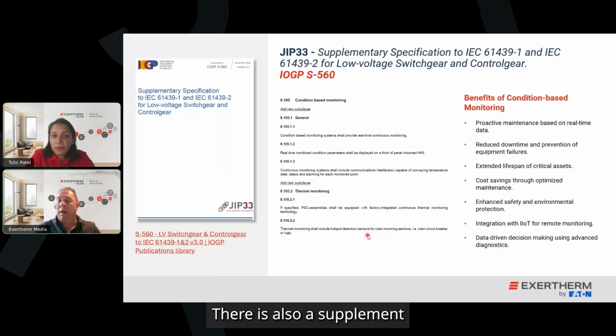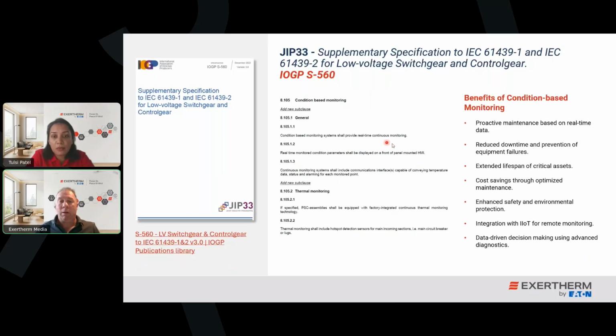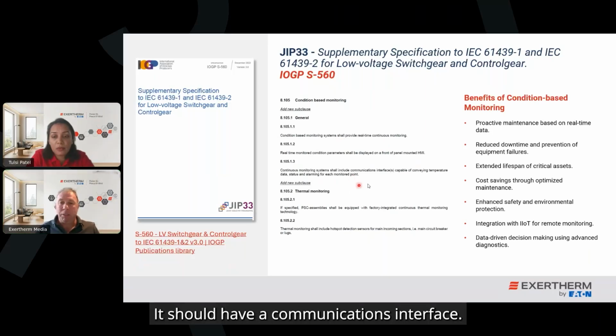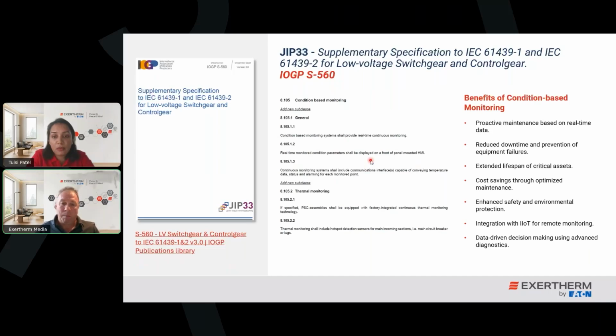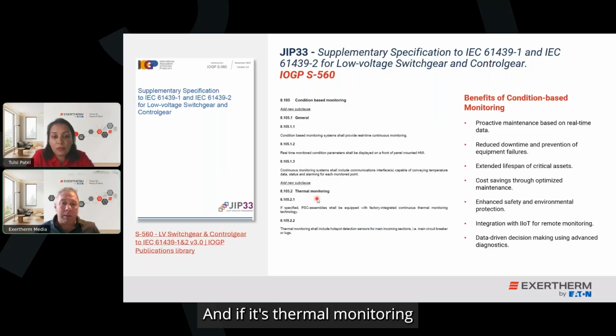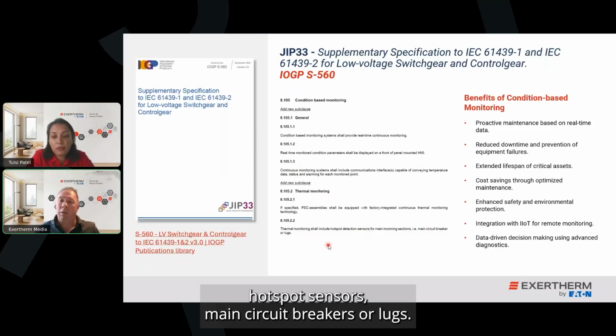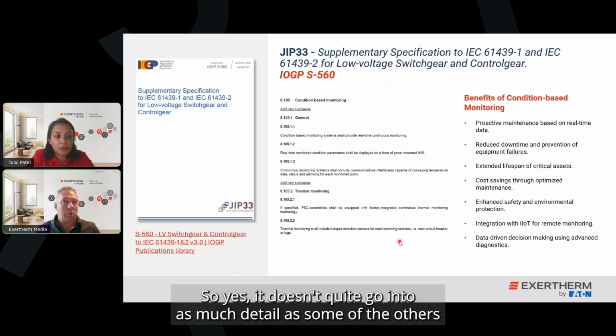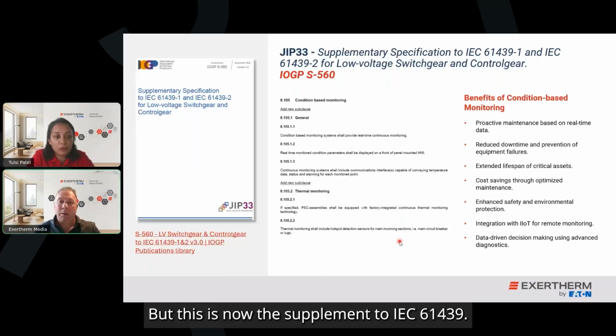There's also a supplement which sits alongside the IEC 61439, the S560. And again, that starts to specify use condition-based monitoring. If you're going to do it, it should provide real time. It should have a communications interface. You should be able to view that data locally. And if it's thermal monitoring that's been put in now, if it's specified, they shall be equipped with factory integrated CTM technologies. And again, it's hotspot sensors, main circuit breakers or lugs. So yes, it doesn't quite go into as much detail as some of the others of exactly where you should place it, but this is now the supplement to IEC 61439.